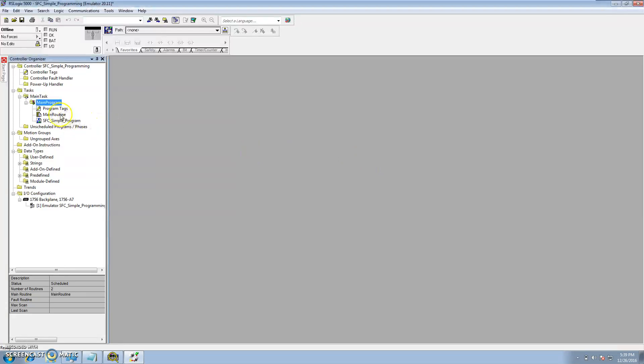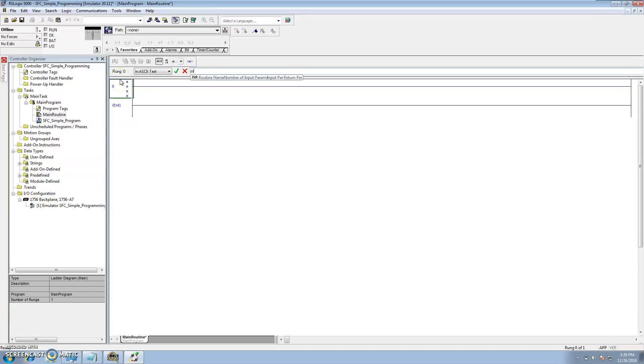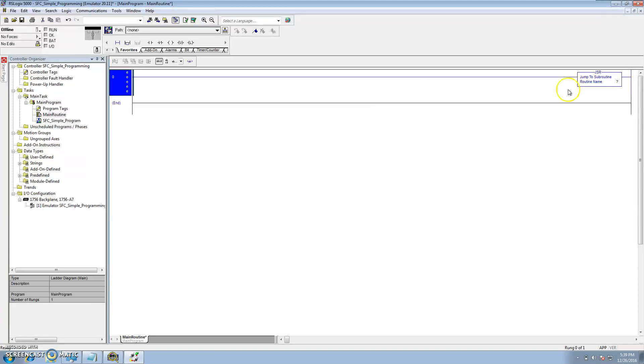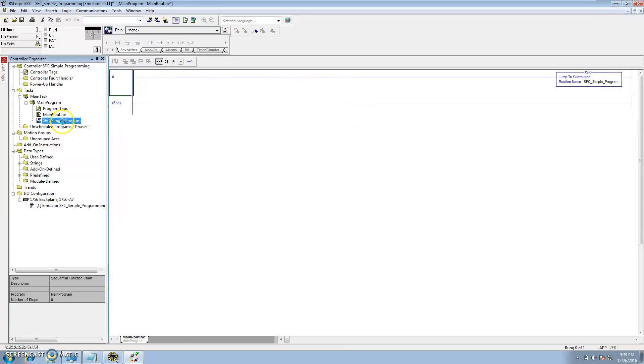At this point, go to the main routine, select the JSR, and point it to the sequential function chart. Once that's done, open your sequential function chart and you can start programming. It always starts at step 0 if it's brand new, which is where you want it to start.